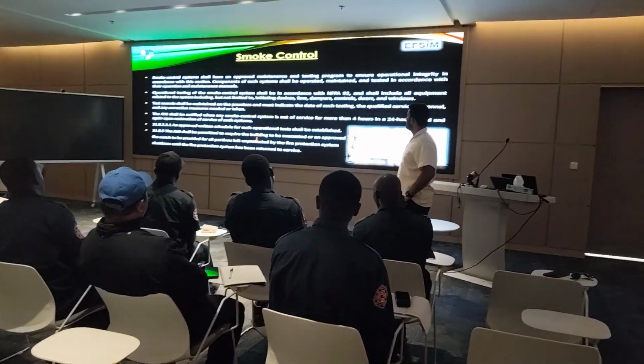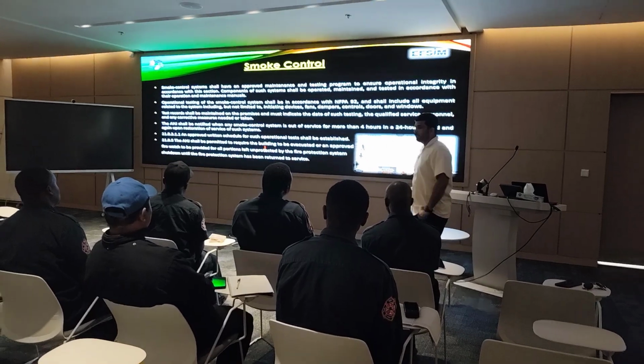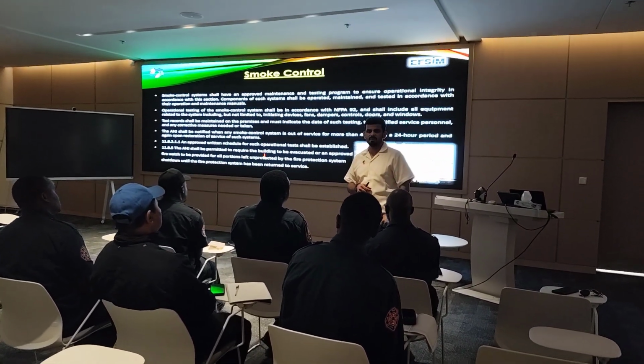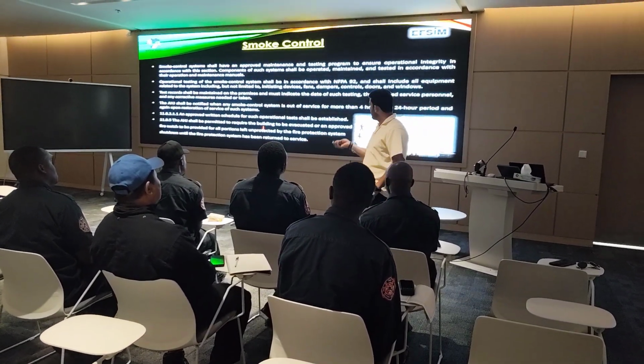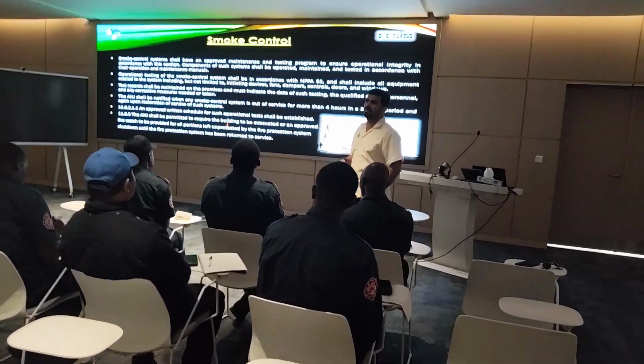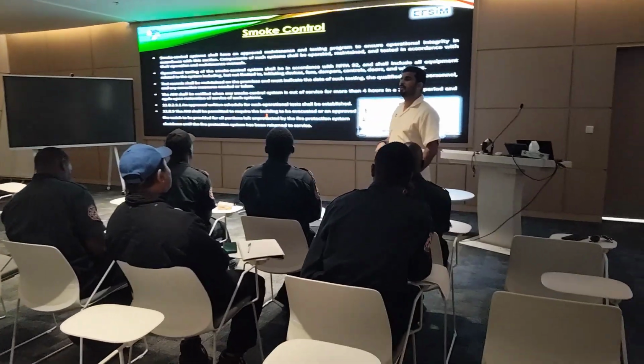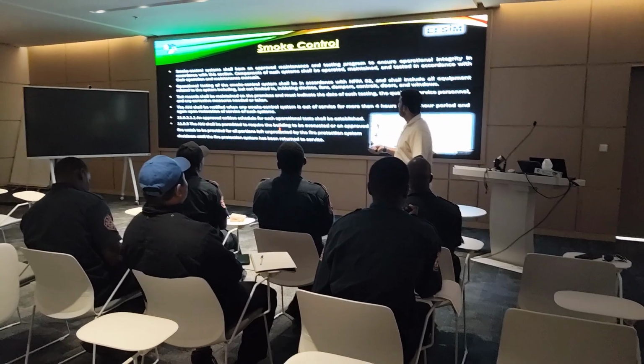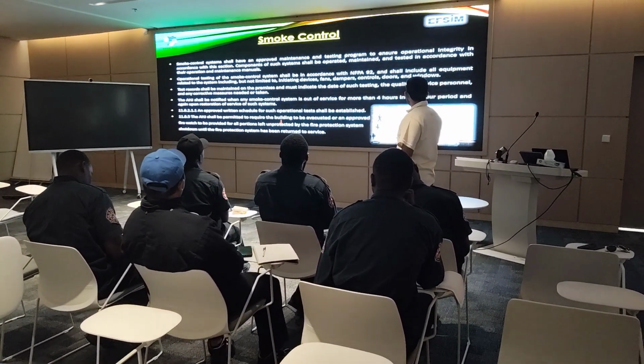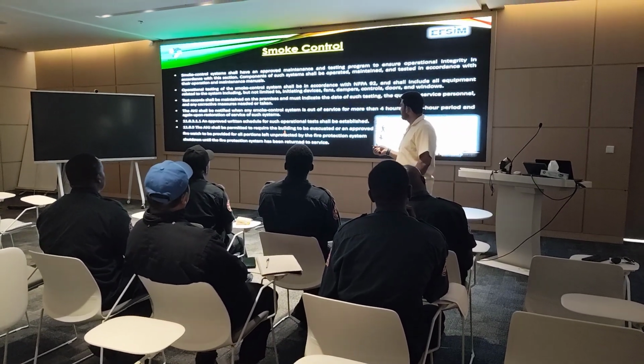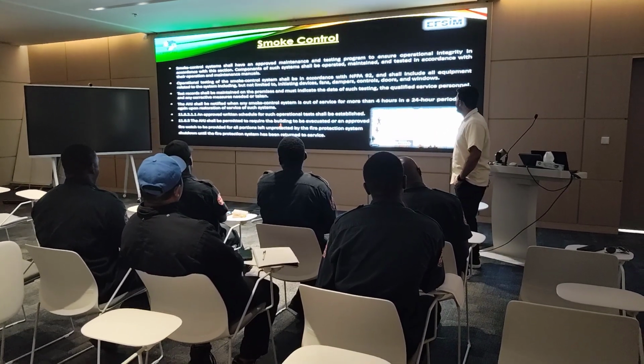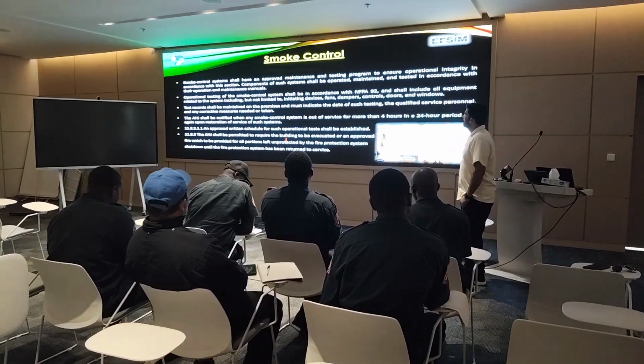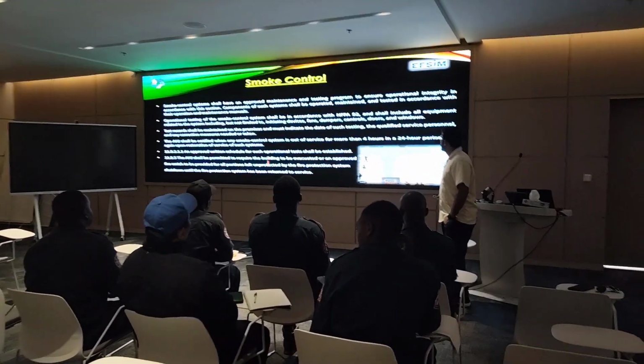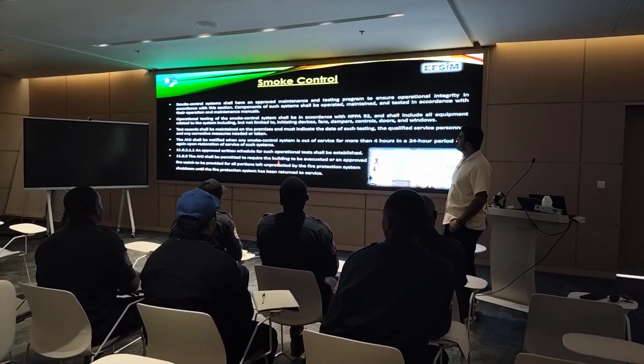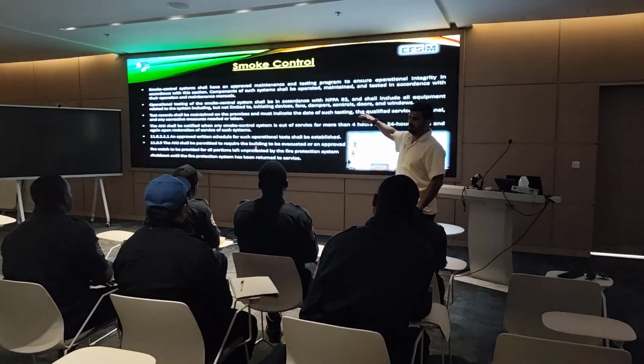A smoke control system shall have an approved maintenance and testing program to ensure reliability. We also install smoke dampers. Smoke dampers are another thing used to control smoke in multi-story buildings, and especially hotels. Such a system should be operated, maintained, and tested in accordance with the operation and maintenance manual. Operational testing of the smoke control system shall be in accordance with NFPA 92 and shall include all equipment related to the system, including but not limited to initiating devices, fans, dampers, controls, doors, and windows. These are all part of smoke control.